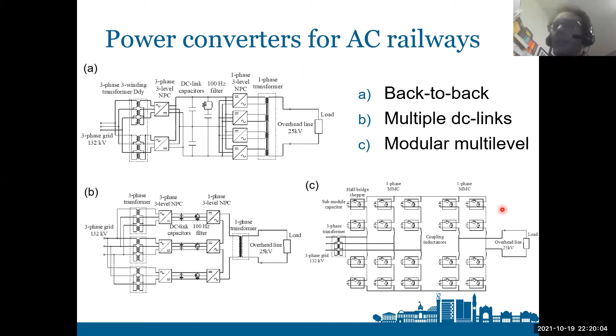In terms of quality of the waveforms, the three converters have a slightly different quality. And in this simulation, we have compared the voltages and the related currents of these three topologies. Obviously, the better quality is achieved by the MMC, where we need around 11 modules to obtain the 25 kV. Then the multiple DC link is the second best, and the back-to-back converter is slightly worse than the others, but is still quite good.